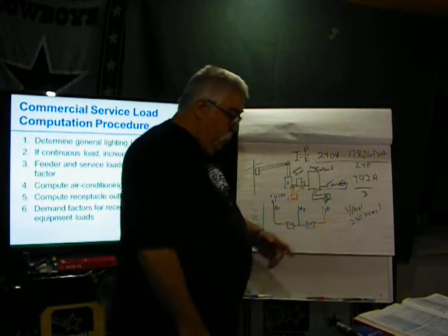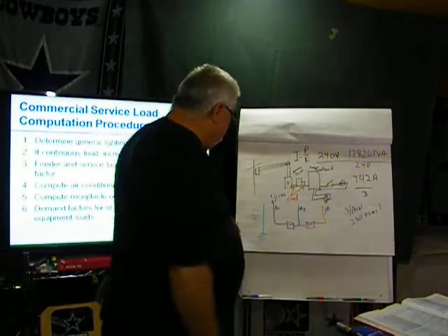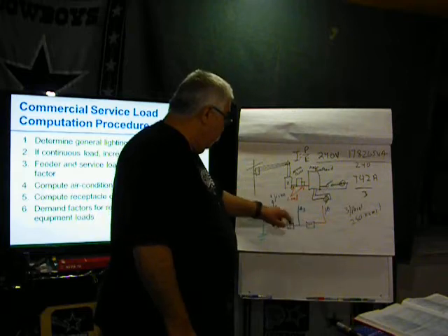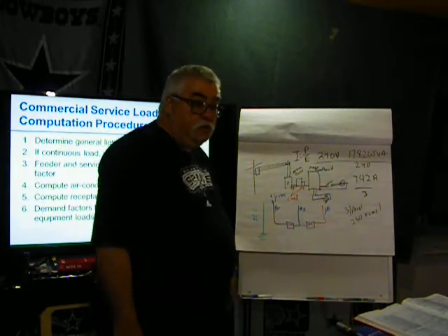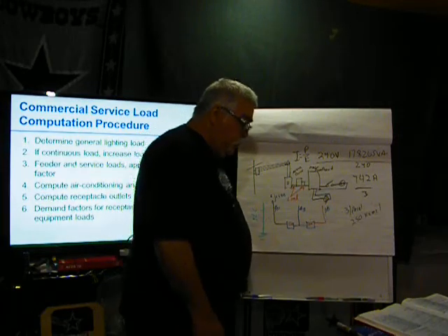So I can downsize it. In the book it says, I'll get into that later in a bit. But what I was talking about is your grounded wire can't be smaller than your GEC. So your grounded wire, which is your neutral, can't be smaller than your GEC.